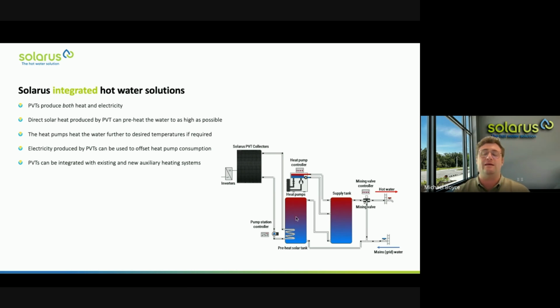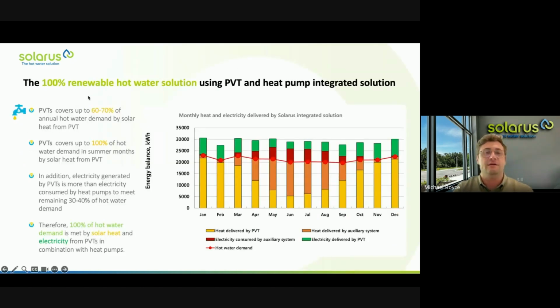Now, this preheat tank in summer can reach temperatures of about 75 degrees Celsius. From there, we've got a supply tank that's connected to a heat pump or your auxiliary. If the temperature in the supply tank is below 60 degrees in the built environment, only then will the heat pump come on to keep this tank at 60 degrees Celsius. We've got a mixing valve, and then it goes out into the building. And this is generally your monthly heat and electricity delivered by the Solarus integrated solution.